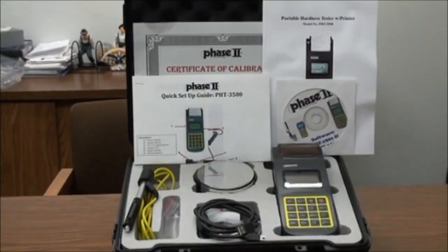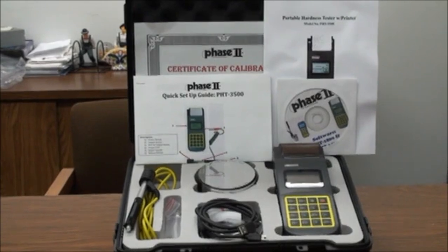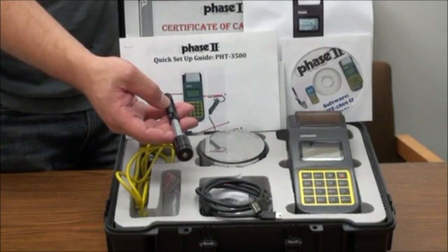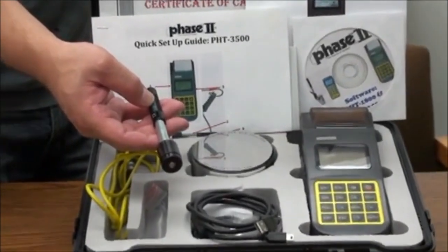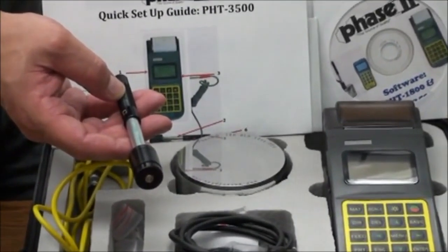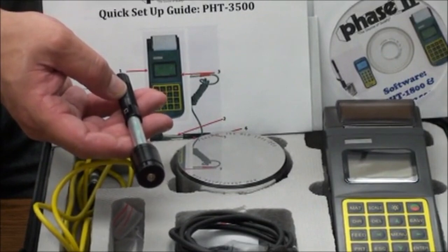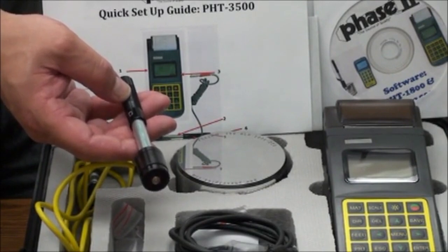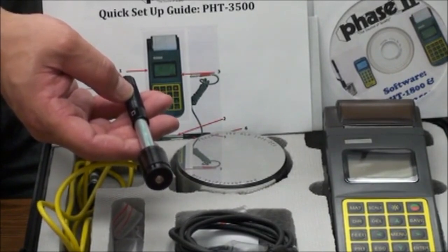This is an instructional video detailing the applications and functions of the Phase 2 PHT 3500 portable hardness tester. The PHT 3500 is designed to test metals, primarily steels, cast iron, aluminum alloys, and copper alloys. The technology incorporated is based on the Leeb system of hardness. A carbide ball is spring-loaded and impacts the workpiece with a given force. The rebound velocity is then measured and converted to a hardness value in Leeb, which can be converted automatically and can be read in any number of scales, which is selectable prior to testing.